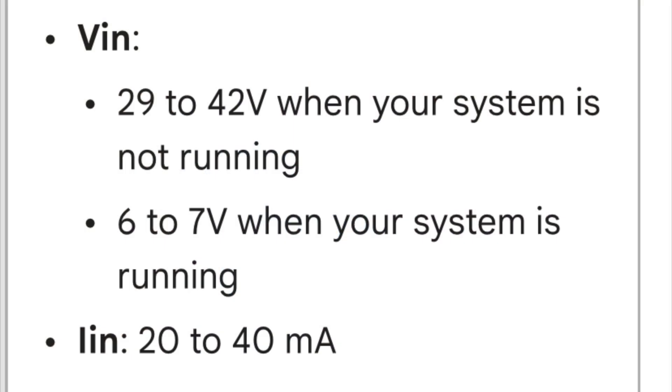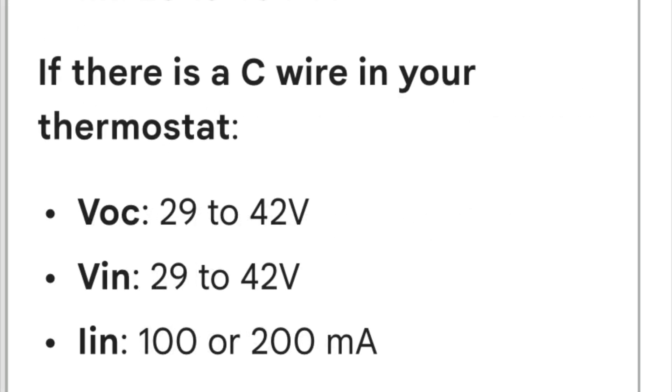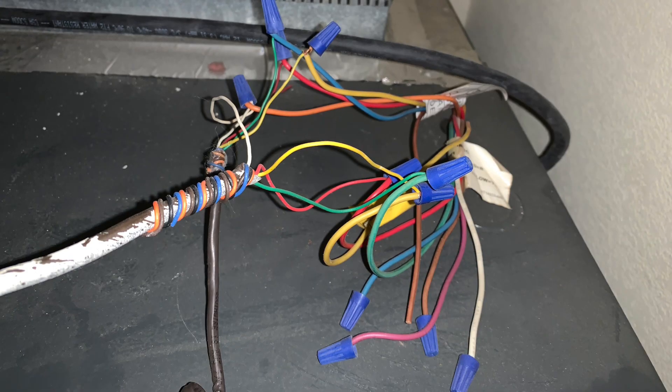Let's read the specs. If the C wire is not connected, it should be 29 to 42 volts when the system is not running, and 6 to 7 volts when it is running, with 20 to 40 milliamperes. When there is a C wire, it should be 29 to 42 volts and 100 or 200 milliamperes.